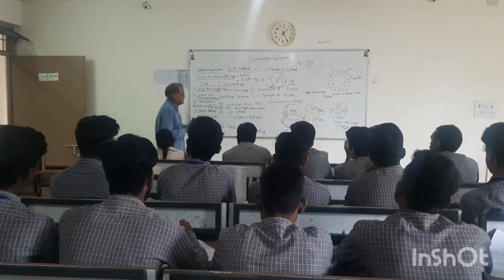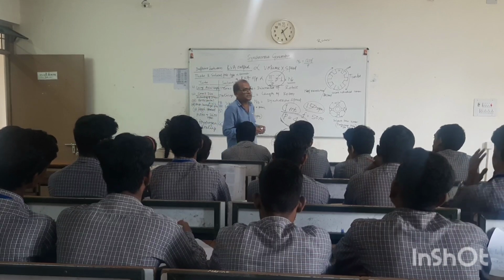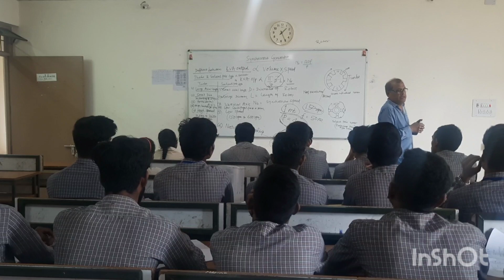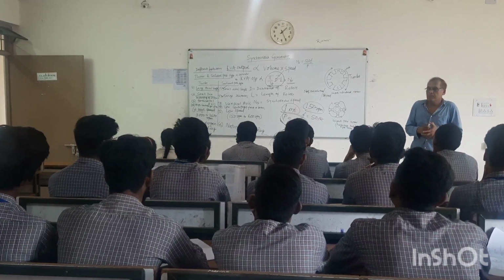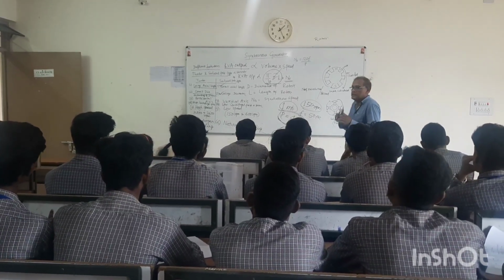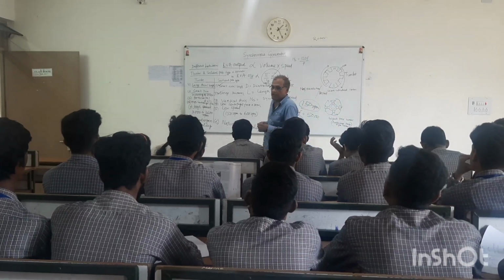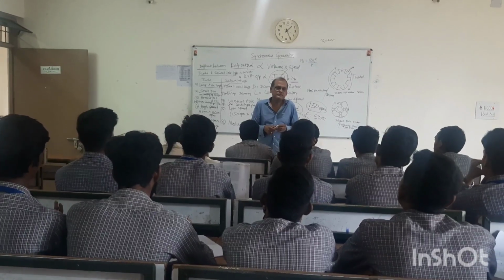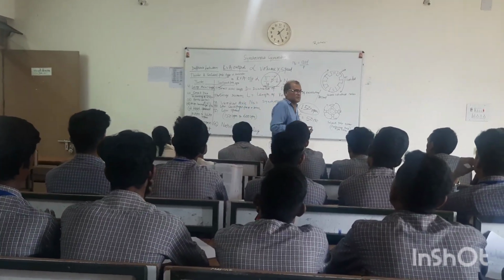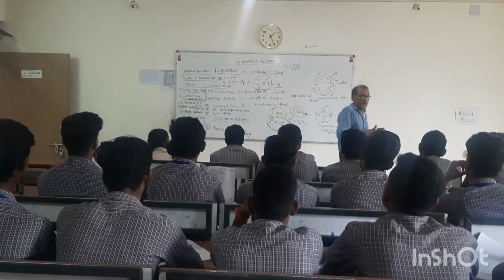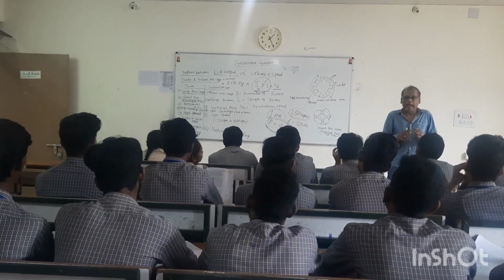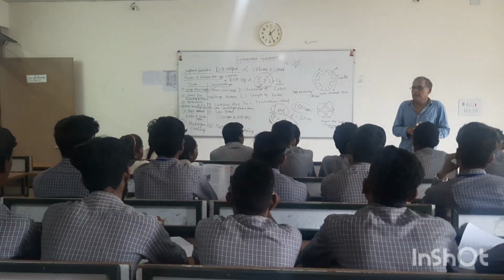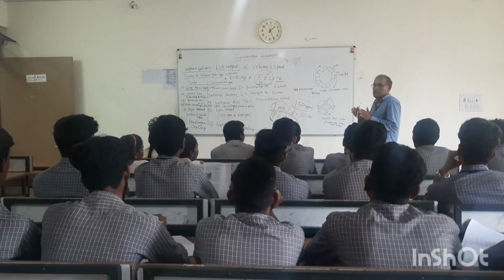Then the last point, that is the difference in cooling. Cooling is a big hurdle while designing alternators, basically in the case of turbo alternators. Above 100 megawatt, hydrogen cooling is a must to limit the temperature rise.